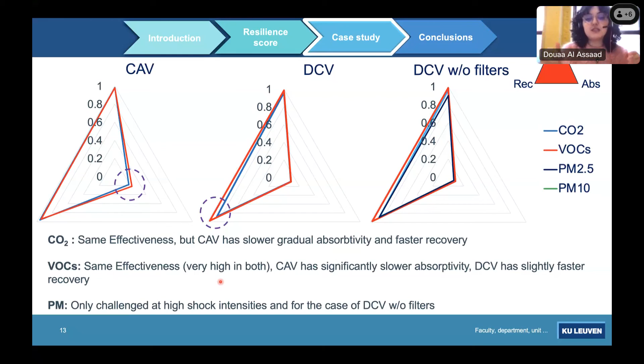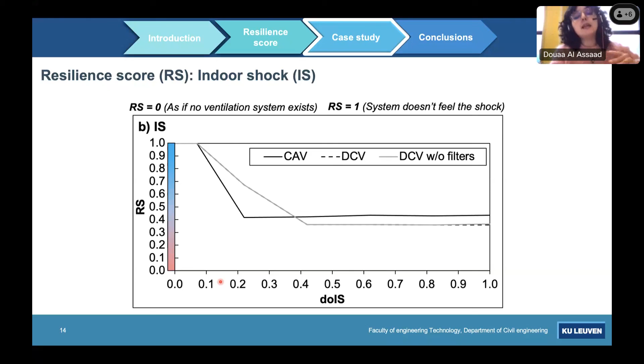We see that up to a degree of shock of 0.4, corresponding to around 20-25 additional occupants, the DCV performed better than the CAV, but beyond that, the CAV had higher performance. So this gives us an idea of how we can operate our building and our system when a shock occurs. It also gives us reason to think, for example with DCV, about how we can design the minimum flow rate in demand control ventilation to face such shocks.